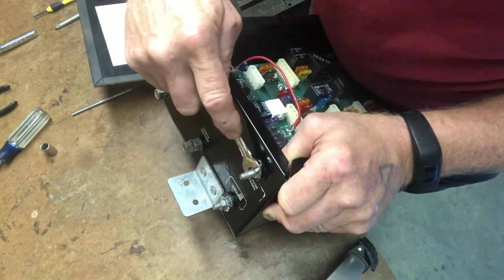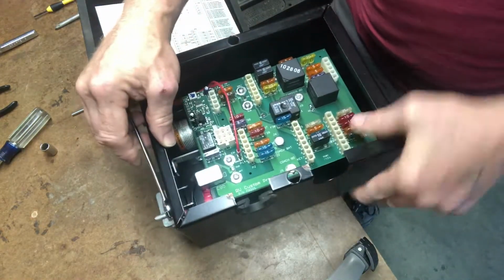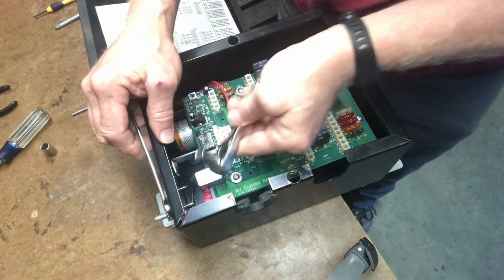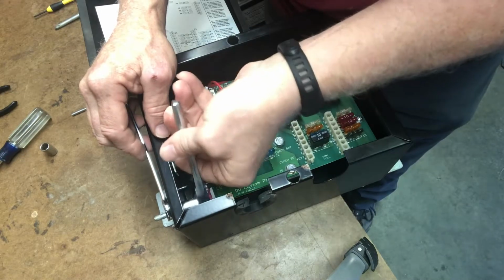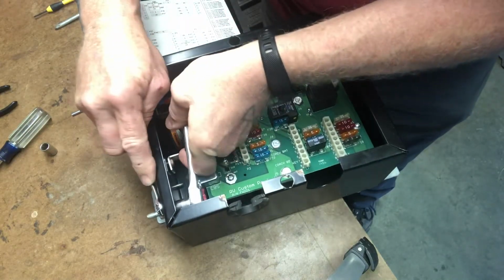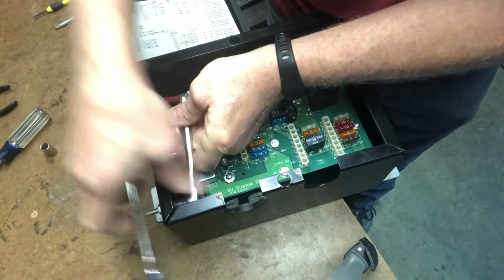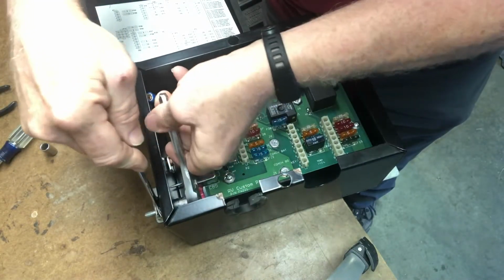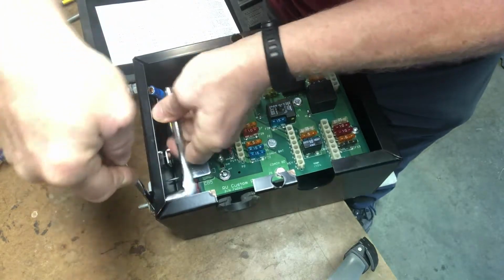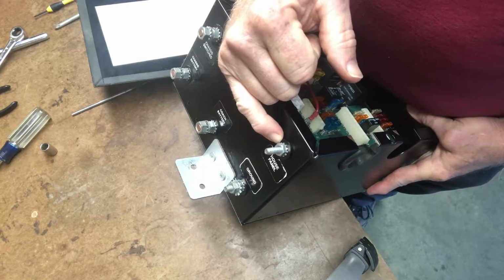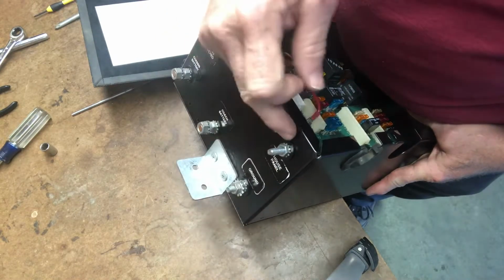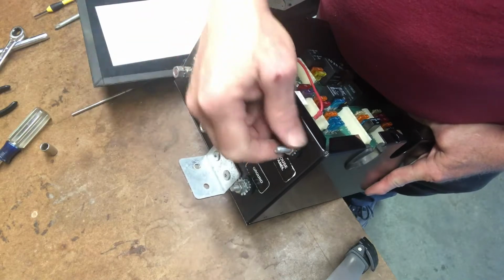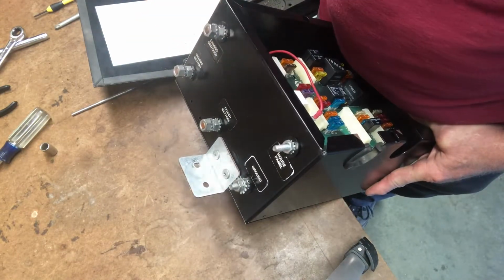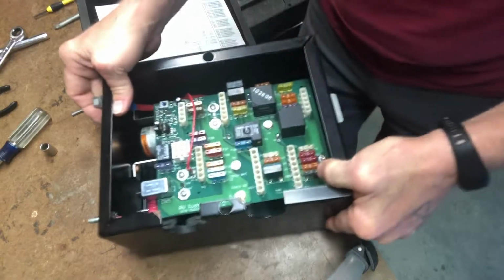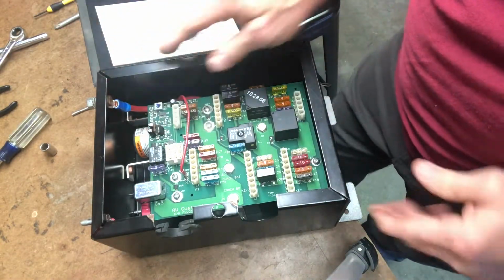Now you want to be careful, because here's where you need a backup on the opposite side. You don't want to just start cranking on this. This has a star washer right here. You don't have to make it so tight that you crack through this insulating material. The star washer will keep things locked. You're good, okay? So that's the complete reassembly of this unit.